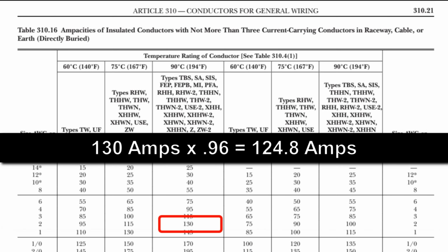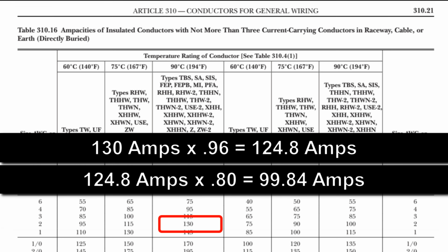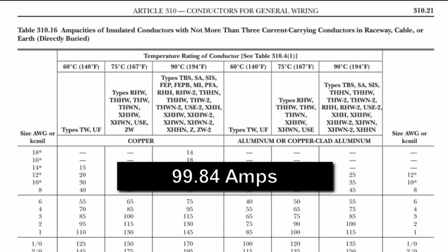Let's run the numbers. 130 amps times the 0.96 temperature adjustment equals 124.8 amps. 124.8 amps times the 80% derating for more than 3 current-carrying conductors equals 99.84 amps. Okay, I have to admit, this is a conundrum. 99.84 amps is less than 100 amps. Technically, according to the letter of the code, I should increase the conductor size to 1 AWG. But I'm rationalizing that 99.84 amps is only 0.16 amp less than 100 amps. It's 160 milliamps. And a difference of 160 milliamps is virtually no difference on a 100 amp circuit. It's 1.5 tenths of an amp.